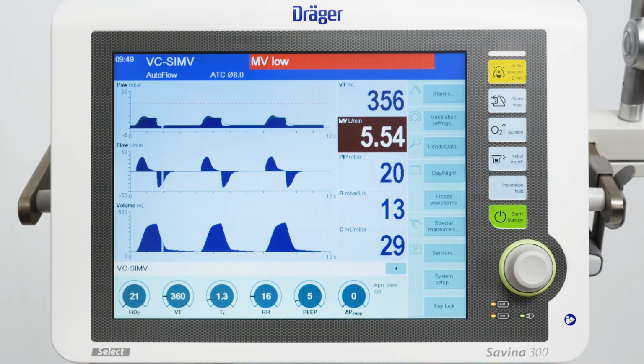The background color of the alarm message field indicates the priority of the active alarm. If several alarms occur simultaneously, the alarm with the highest priority is displayed first. High priority alarm messages that are no longer active are displayed in the background color of the alarm message field. The parameter box of the parameter triggering the alarm flashes in the color of the alarm priority.